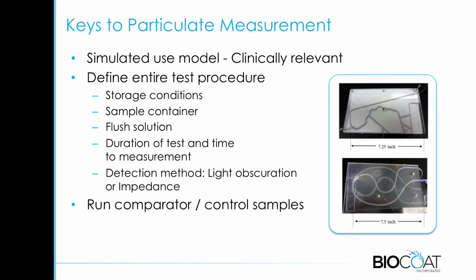The keys to particulate measurement are several-fold. As the FDA mentions, you need to use a simulated use model, and it needs to be clinically relevant. For example, ASTM has a model that is useful for stent retention. For a cardiology device, you may want to use that model to track the device through, collecting the flush solution afterwards. However, in a peripheral model, you may want a more serpentine, winding, tortuous path. You need to define what that model is and why it is clinically relevant for your device and your coating.